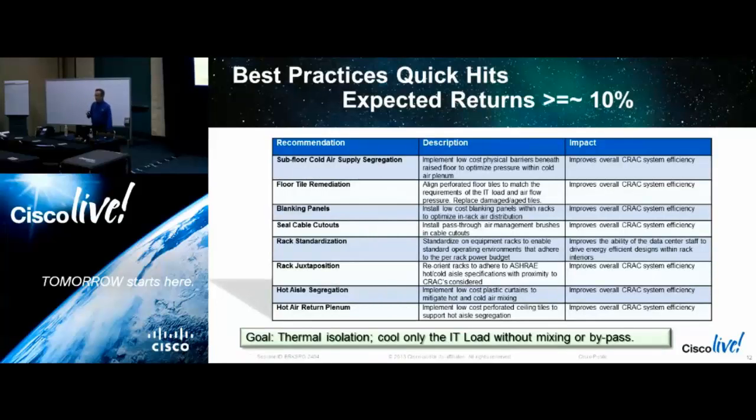It's nothing else. Now, when you look at the bottom of that rack, where the cables come up through the floor, there's any number of third-party products that'll let that cable up, but not the air. Not rocket science. Plug the hole. Looking down at that perf tile, is that the right airflow? Is it right position-wise in front of the rack? It's not under the rack, sliding under there. You don't want it under there. You want it in front of the rack.